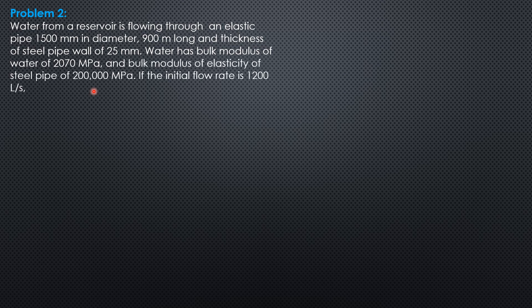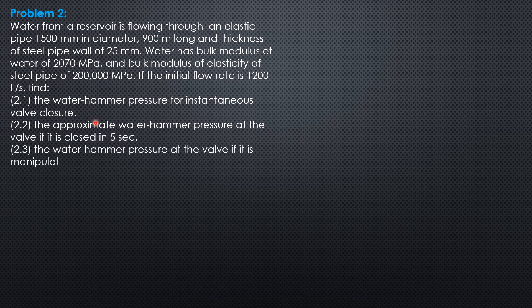Water from a reservoir is flowing through an elastic pipe 1,500 mm in diameter, 900 meters long, with a steel pipe wall thickness of 25 mm. The bulk modulus of water is 2,070 MPa and the bulk modulus of elasticity of the steel pipe is 200,000 MPa. The initial flow rate is 1,200 liters per second. Find the water hammer pressure for instantaneous valve closure.